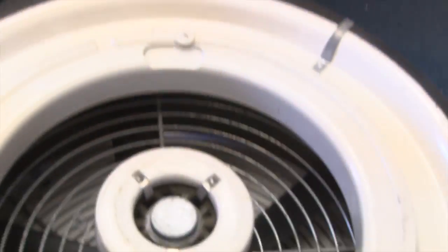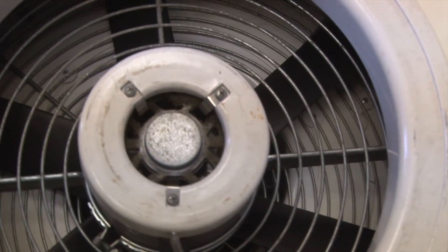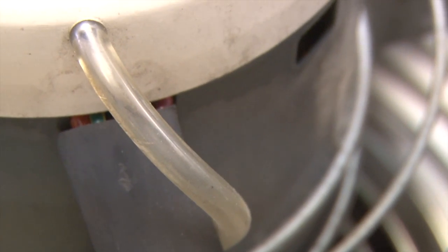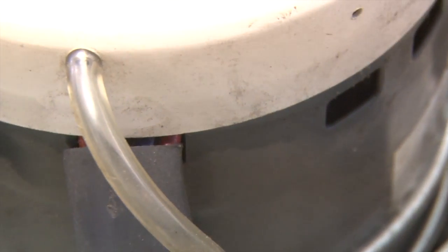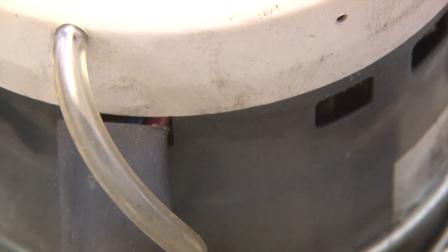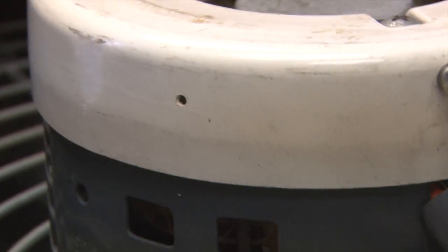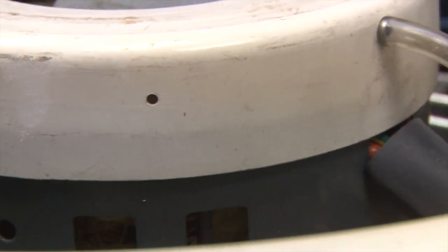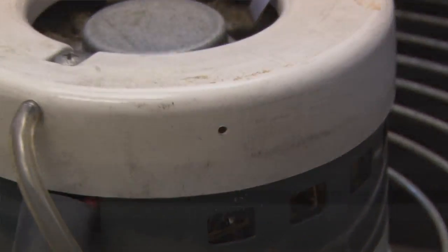It's really similar to what the Model 3 fan is doing, and then how it's relaying that information to the DG700. So the Model 3 fan has a white ring mounted on it, and the white ring is connected to the pressure tap that you usually connect your red tubing to. It's on the top of the fan housing. And the white ring also has 3 or 4, I think it's 4 small holes drilled in it, and those holes are the pressure sensing holes. And so it's simply a pressure sensor. It doesn't calculate or anything of that nature, but it's a pressure sensor of a known size with known sized holes drilled in it. And that pressure is transmitted back to the DG700.